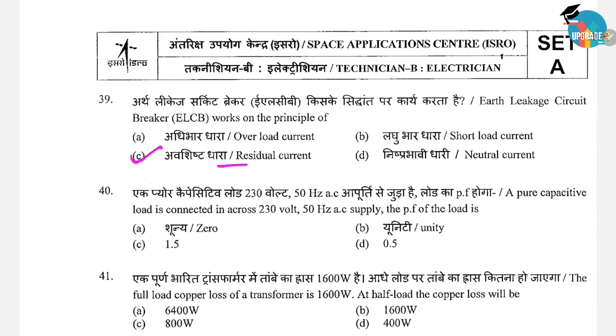The full load copper loss of a transformer is 1600 watts. At half load, the copper loss will be calculated as (1/2)^2 multiplied by the full load copper loss, giving 400 watts. So the correct option is half load copper loss equals 400 watts.